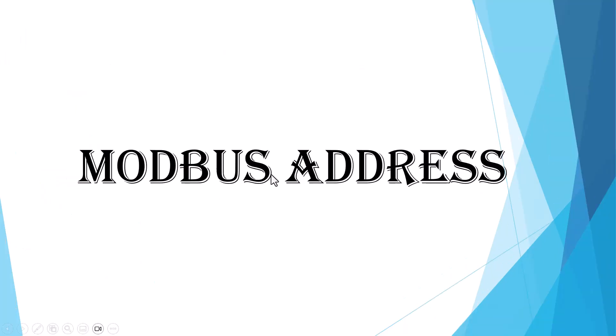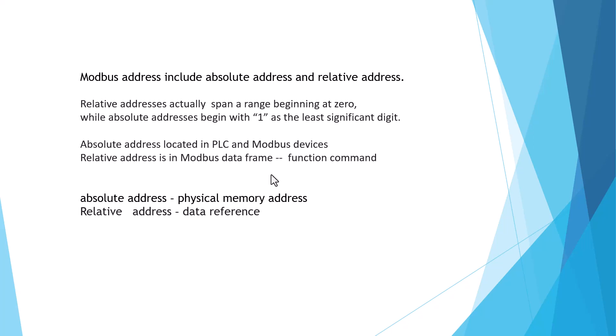Hello, today we talk about Modbus Address — including Absolute Address and Relative Address. Relative Address actually begins at zero. Absolute Address begins with one. Absolute Address is used in the PLC and Modbus device. Relative Address is used in the Modbus data frame function command. Sometimes people call Absolute Address a fixed memory address, and Relative Address is called a data reference.